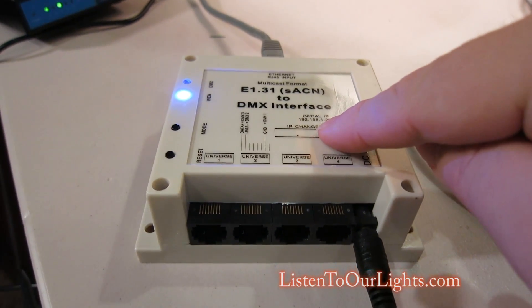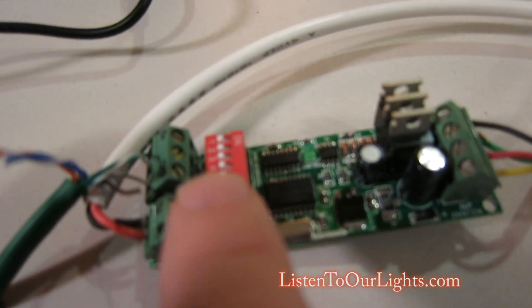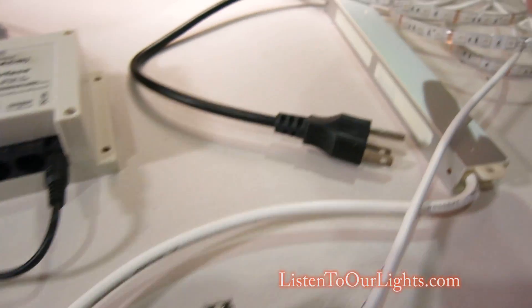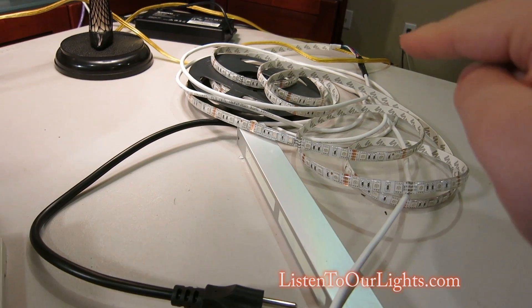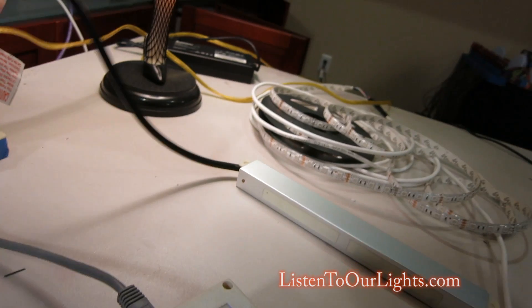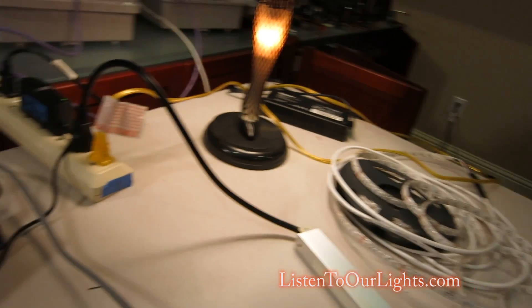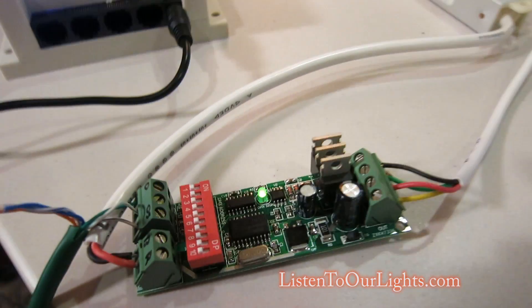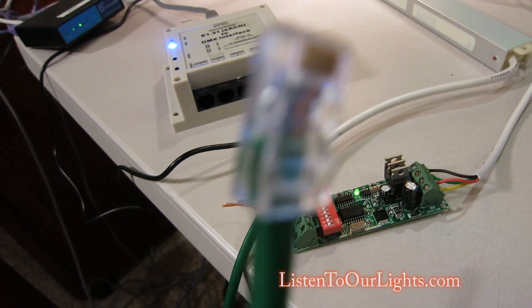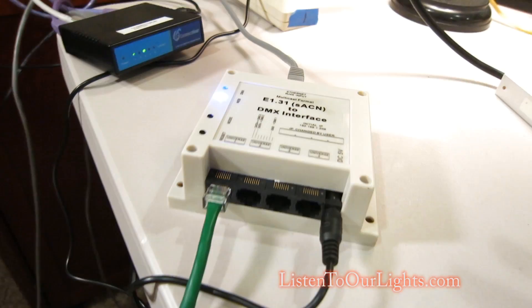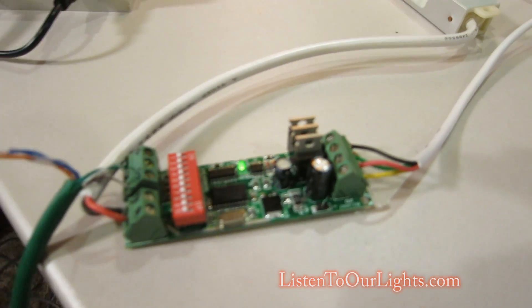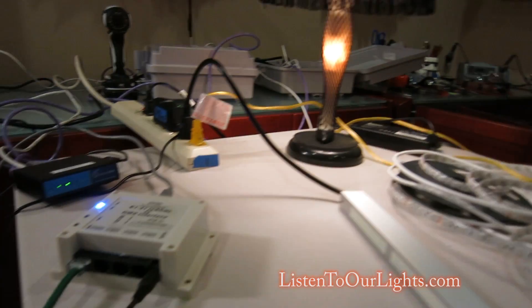Now, the universe is set by the configuration in the bridge. The channel is set by the dip switches. And by default, if you don't have anything set on this particular one, it is channel 1. So, what I am looking at for these lights here, is I am looking at universe 50, channel 1. So, now I am going to try and plug this guy in. The lights will probably flash. That is okay. They did not blow up. They are just powering on. I have a green light here, which means I have power. But, I do not have DMX signal. Why? Because I have not plugged in this guy. So, I plug him into port 1, which I have configured for 50. So, now he is plugged in. The little light is flashing. That means it is getting a DMX signal.